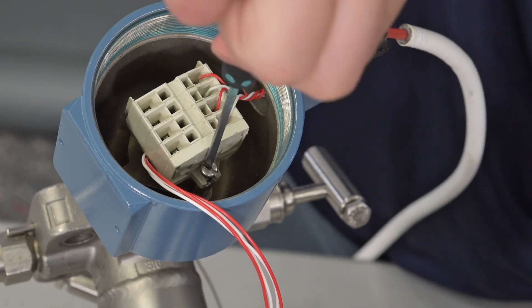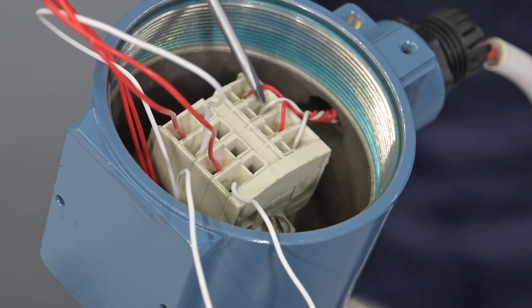Reattach the RTD terminal block and the RTD wires. Make sure to attach red to red and white to white and then screw the cap back onto the connection head.